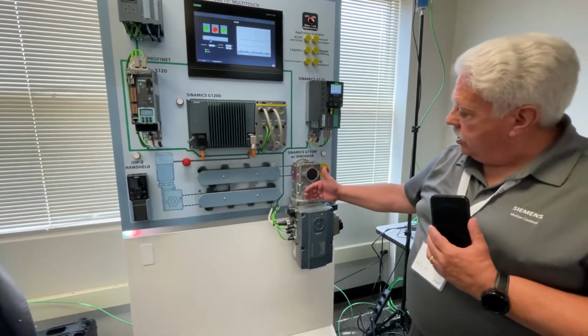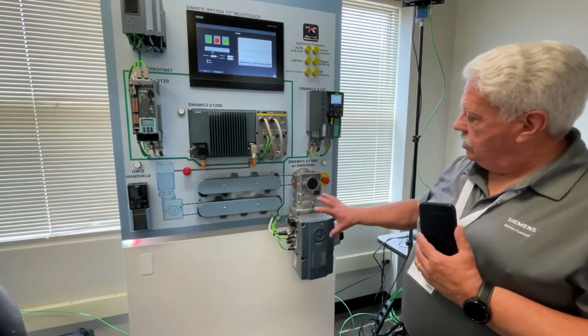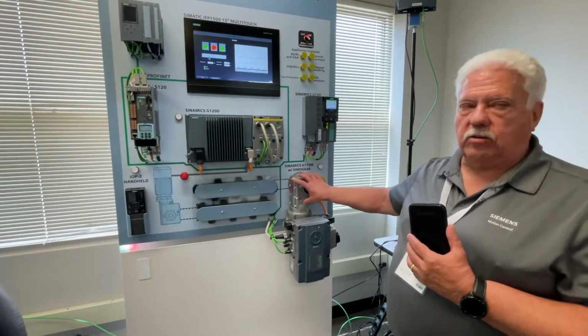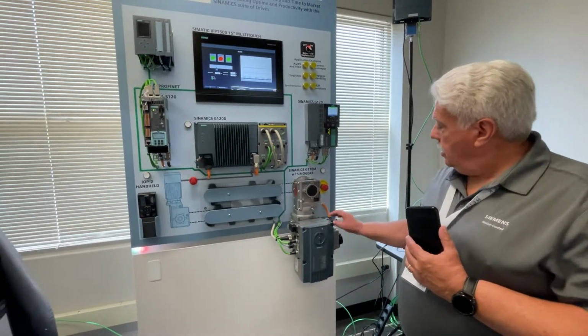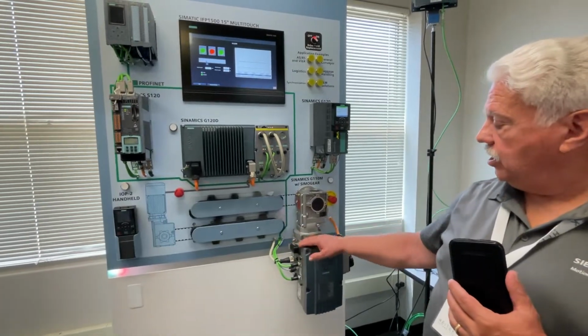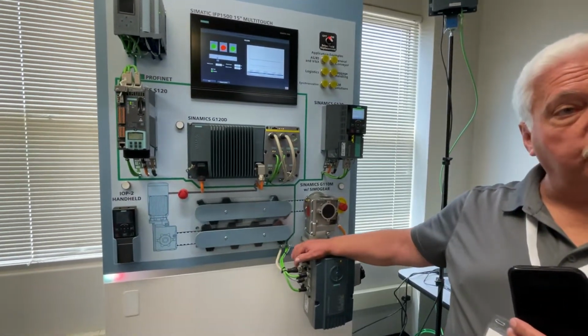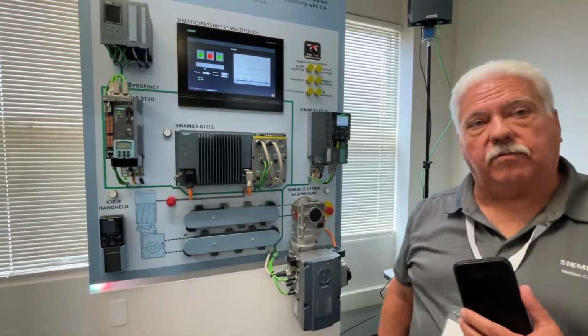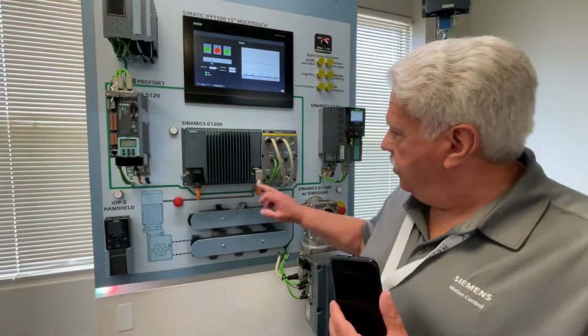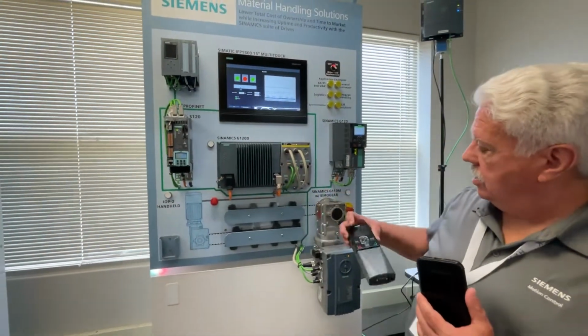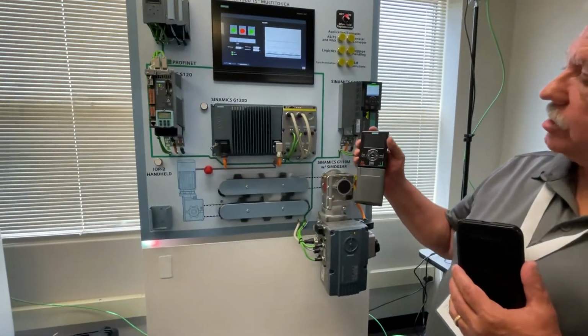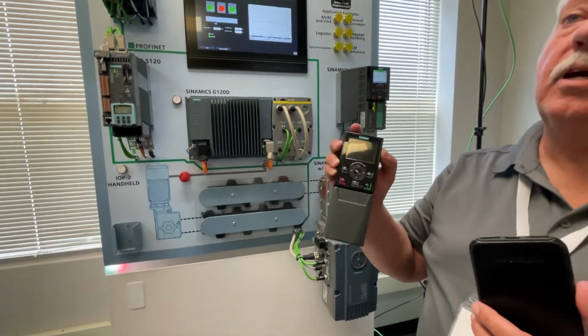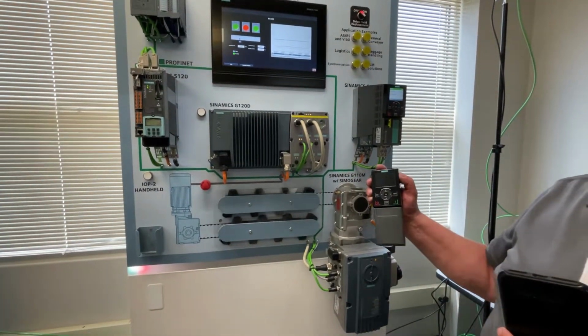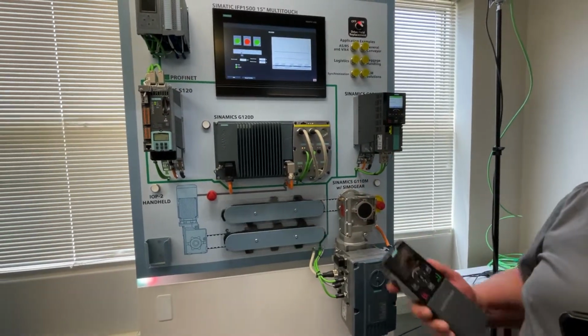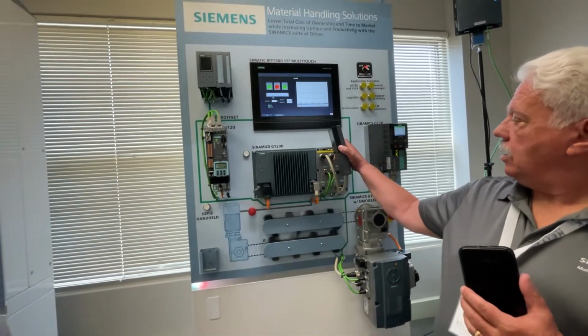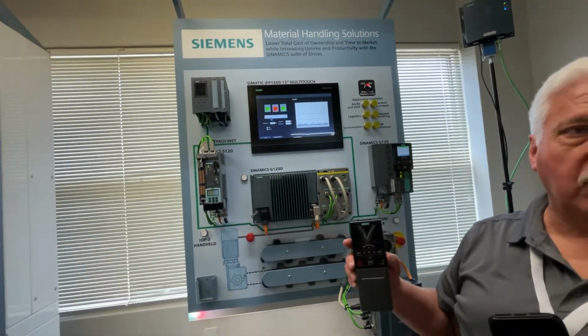In this case down here, we have another drive, which is, again, modular, same basic componentry inside, but this one is designed to mount directly to the gear motor, so it's an integral part of it. Again, service disconnect on the side, power cable in, and we can also daisy chain and come power back out the other side. So we can daisy chain multiples of these together. We program this guy with a handheld, so it utilizes the same screen as this has. These particular screens can have up to 254 different configurations on them, so you can configure multiple different drives out in the field with this one keypad. This one happens to connect via a USB port, or there's also an infrared port on the drive itself.